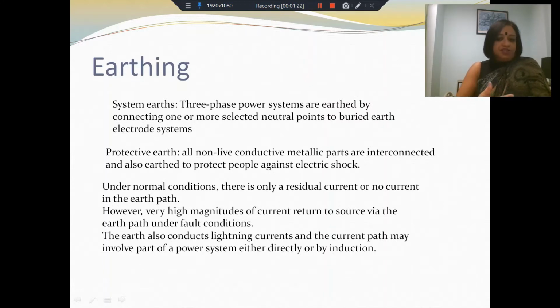Now, under normal conditions, whichever parts of the system are earthed, the earth path should not carry any current. There should not be any residual current in any of the earthed components or in the earth path. However, if you have very high faults in the system, then under these fault conditions a very high current would flow to earth and would find a path back to the source through the earth. Therefore, in these conditions, the earth path can carry very high magnitudes of current. So that's when you have fault currents flowing.